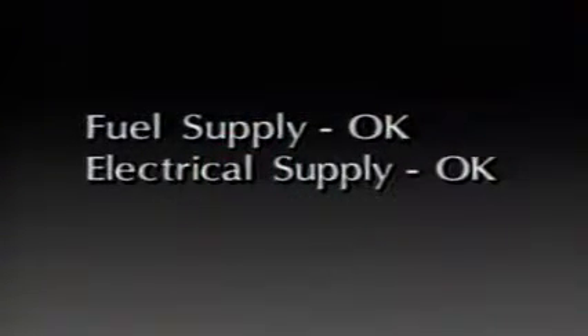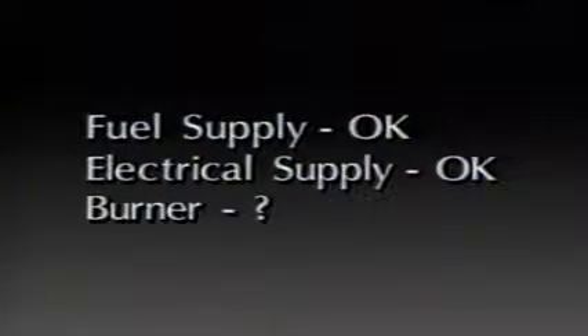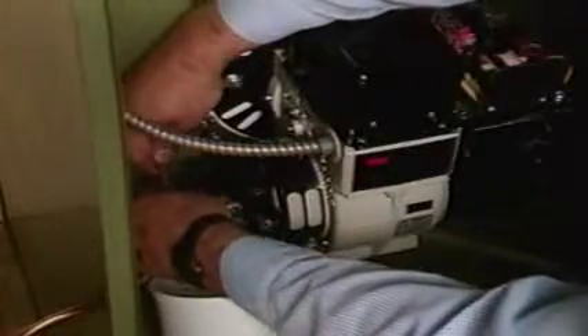If these checks of the fuel supply and electrical supply haven't detected the cause of the problem, it's time to look at the burner itself. Start by disconnecting the fuel supply. Reposition the line so it will deliver oil into a container instead of to the burner nozzle. Tighten the flare nut at the pump discharge fitting. You're ready to reset the primary control. But stop, because you're going to have to be alert to the following conditions which occur almost simultaneously.